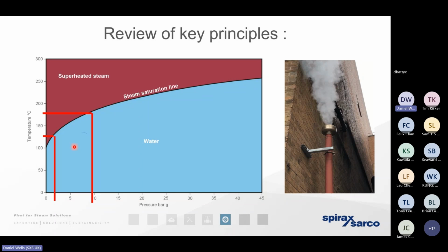We're not getting as much hot water back to the boiler house, so we've got to consume more cold water from the mains. We've got to chemically treat that cold water, and we've got to elevate it up to, in the case of a 10 bar gauge boiler, 184 degrees. So of course we've got to consume more gas, and our carbon emissions are going to increase significantly. So please do remember that those vents are an important and significant telltale in helping us understand the overall health of the wider steam trap population, but most importantly, the efficiency at which we're producing steam and consuming gas.